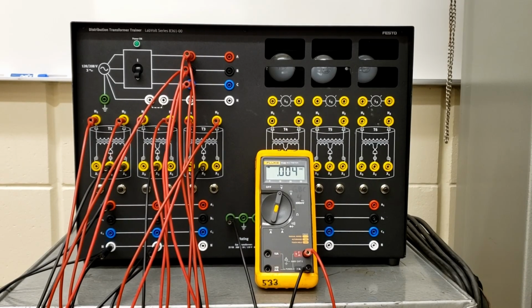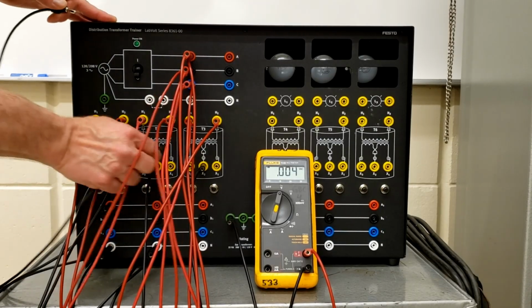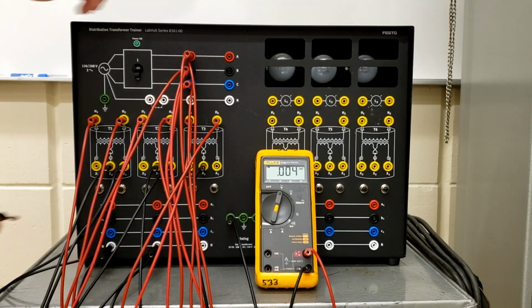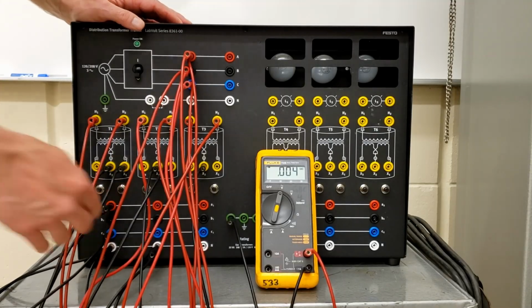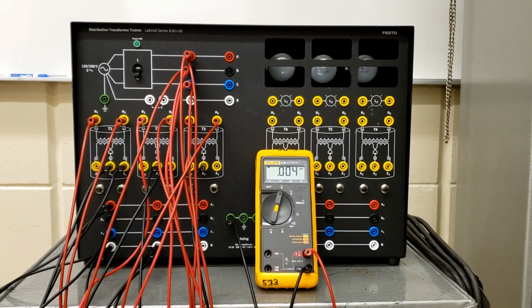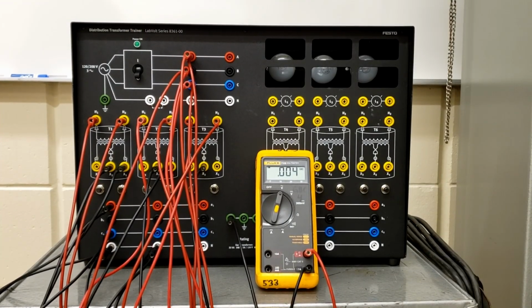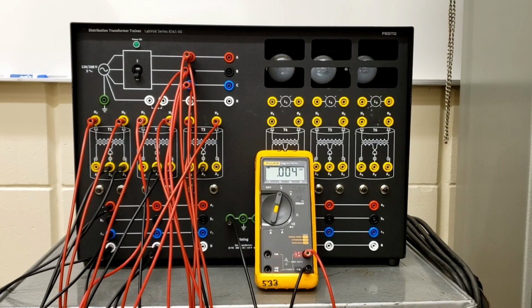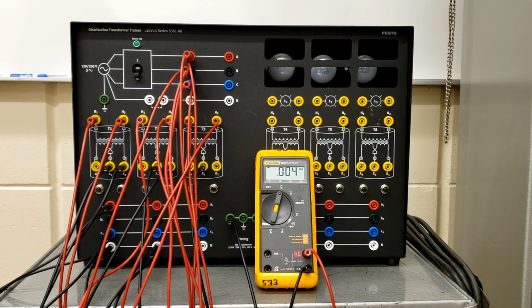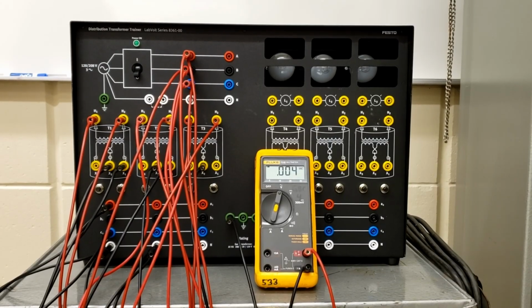X1 of transformer 1 went to A. X1 of transformer 2 is going to C. Is that the same phasing as we had above? Yes, on transformer 2, H1 was being fed by C, so X1 is now going to C.